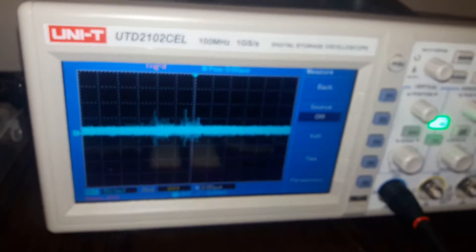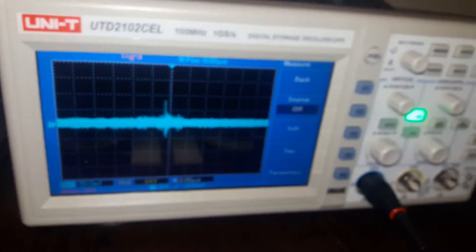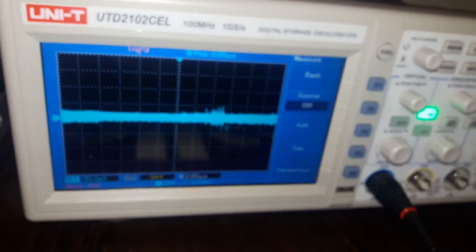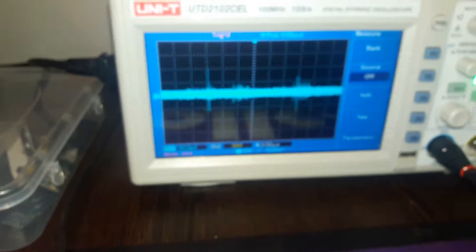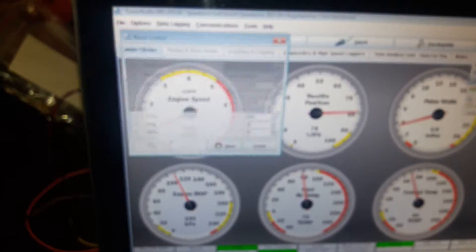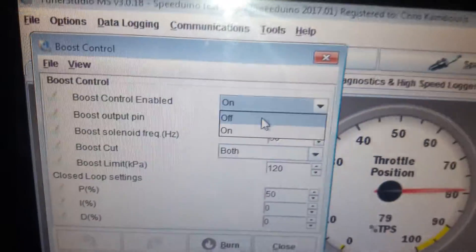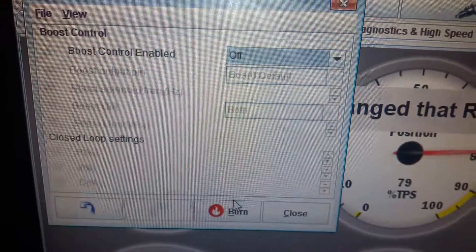Okay, we're not getting anything different. So what I'm going to do now is I'm going to go into the boost table, equal to zero. Nothing changes. Okay, so let's go and switch boost off completely, off. Okay, it requires a cycle power cycle. Nothing's happened on the scope.